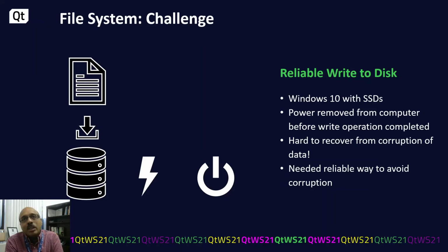The next example is the file system challenge. Again, not a very difficult problem to solve, but oftentimes when we are saving a file to a disk, in our world it was saving a file to a solid state drive on the Windows 10 environment. Being a medical device, our devices almost always run on batteries. They are plugged into the wall, but that's primarily to charge the batteries. Almost everything is driven by the batteries, and this helps a lot when we talk about the exposure to potential AC voltage to the patient or to the operator.